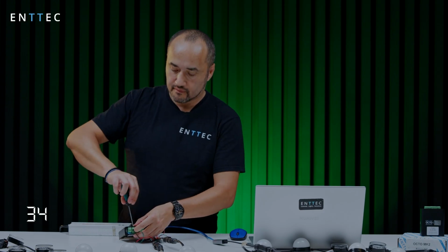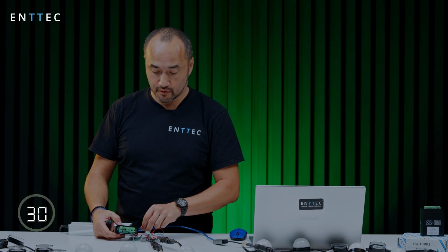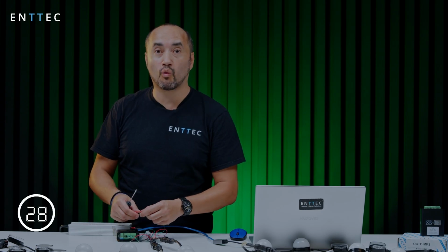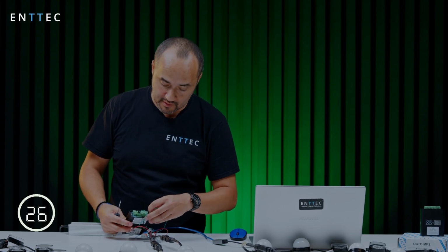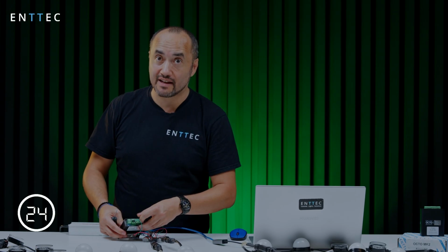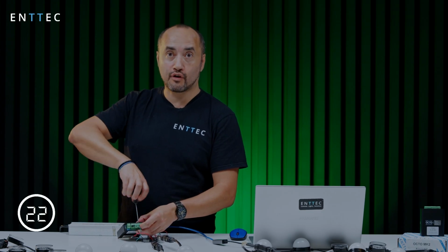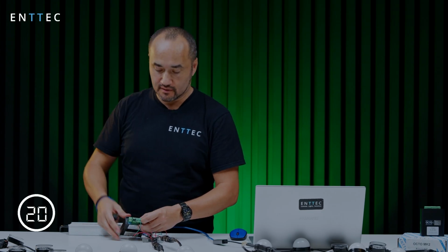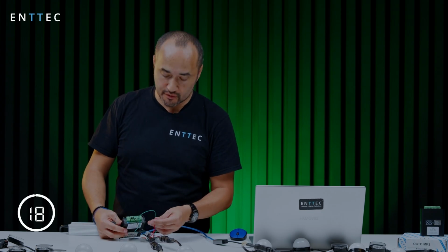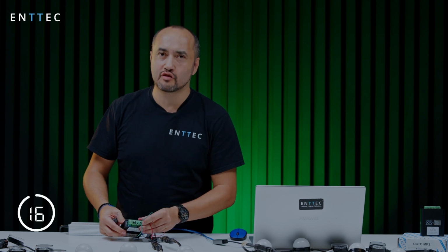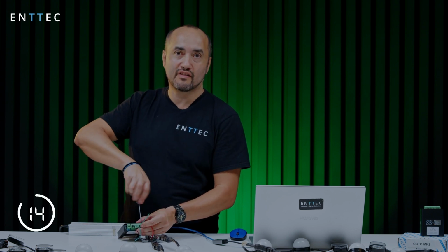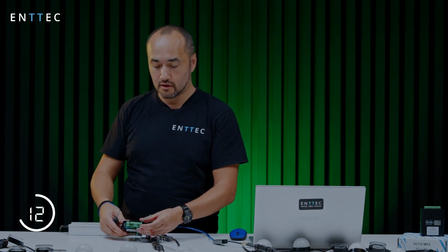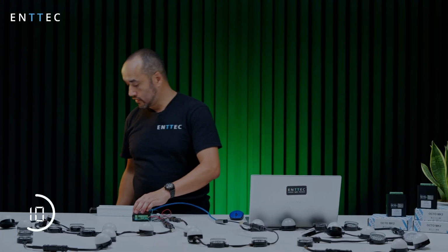Now you'll notice also I've got these terminated with ferrules. A lot of people put wires directly into these screw terminals. Strongly recommend against that. The wires fray, you get bad contacts, your installation fails. It's just bad. Put ferrules, they're cheap and they work. Oh look, done. All connected.